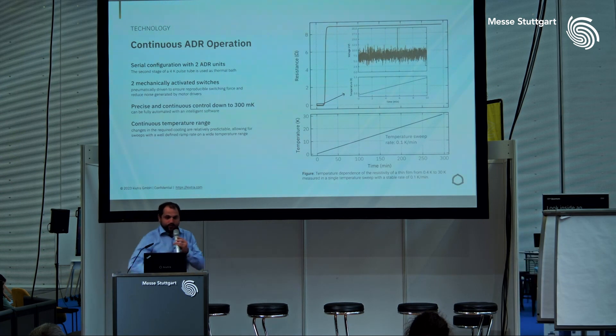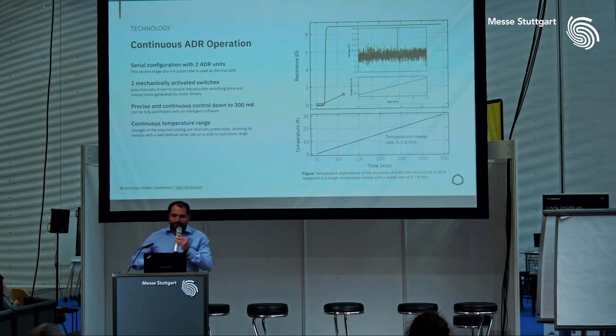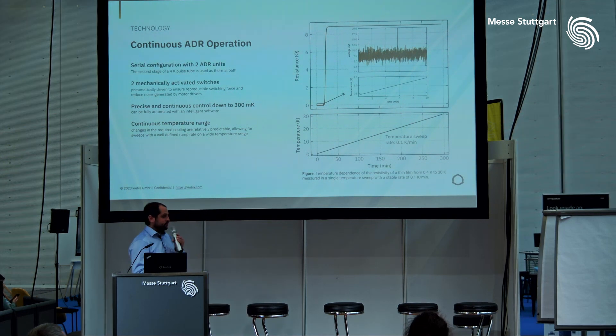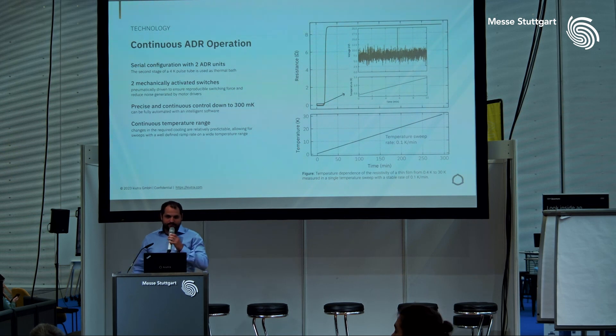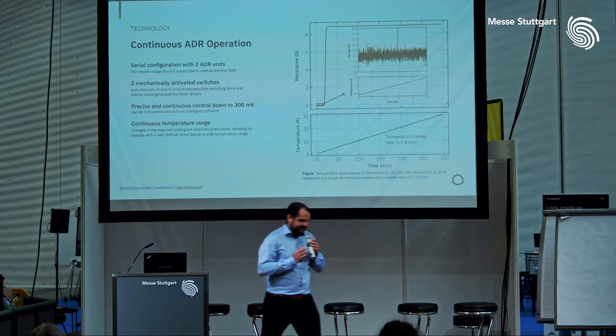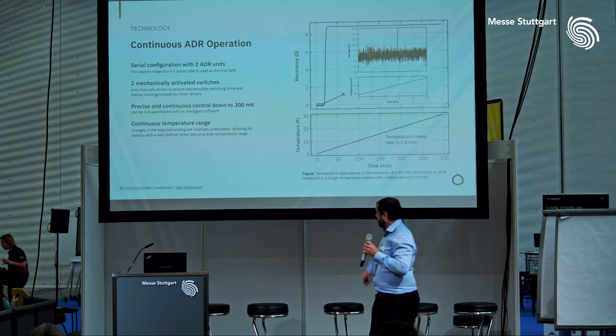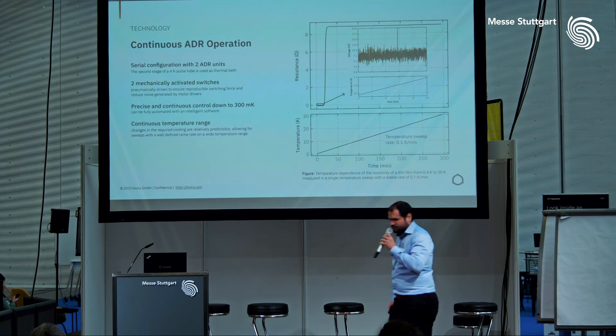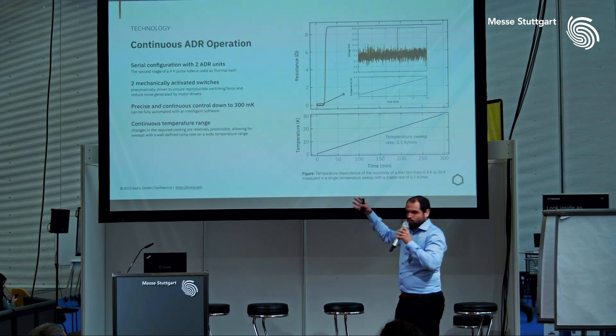We have fully automated this process with intelligent software to offer precise and continuous control down to 300 mK. The ADR also has a wide temperature range, so we can control the temperature at any point between the base temperature and all the way to room temperature.